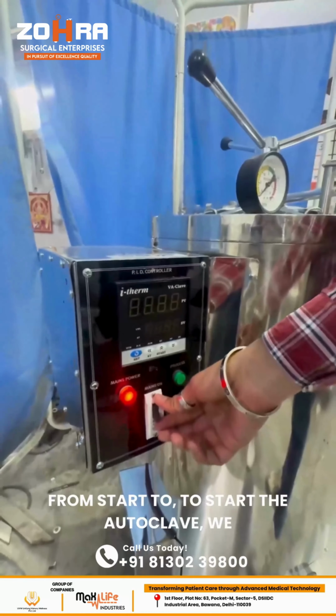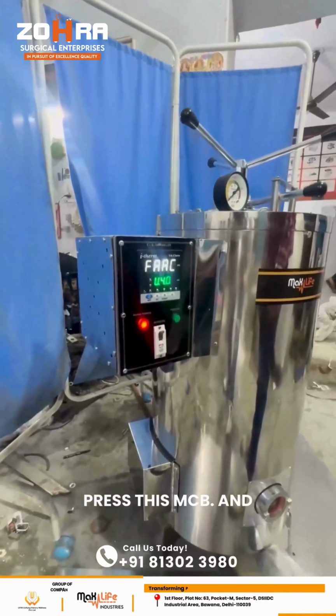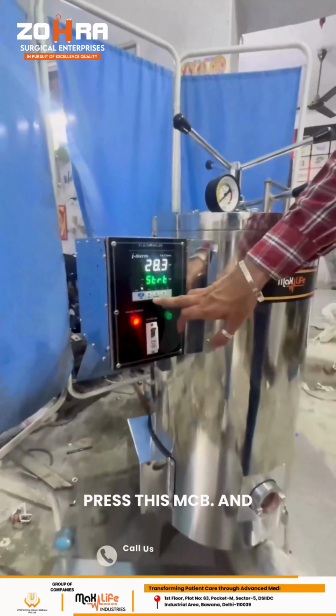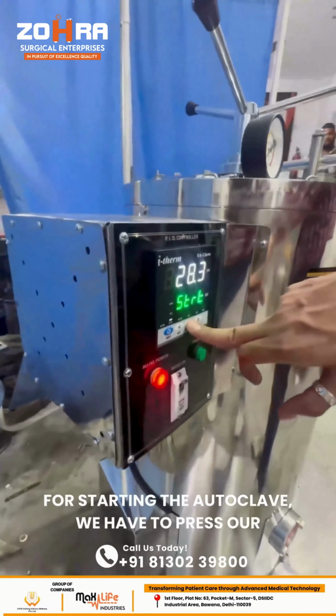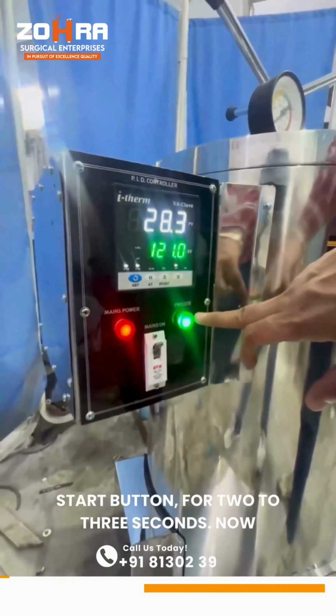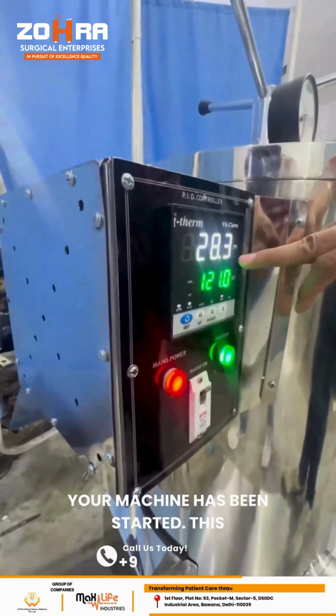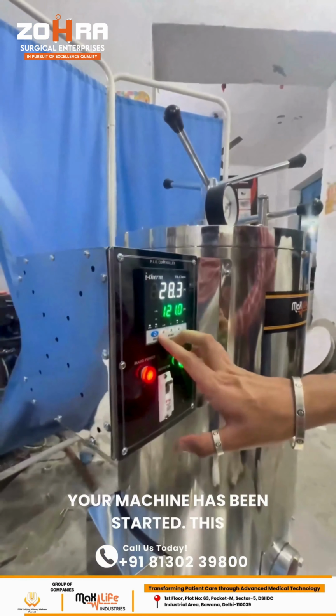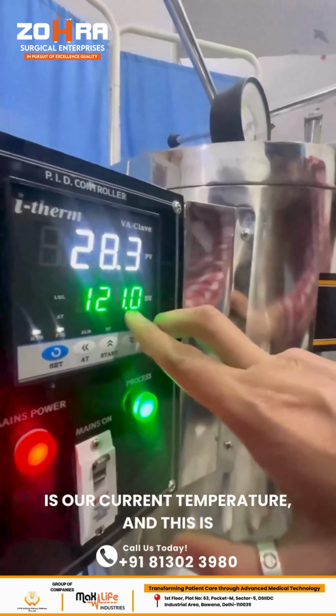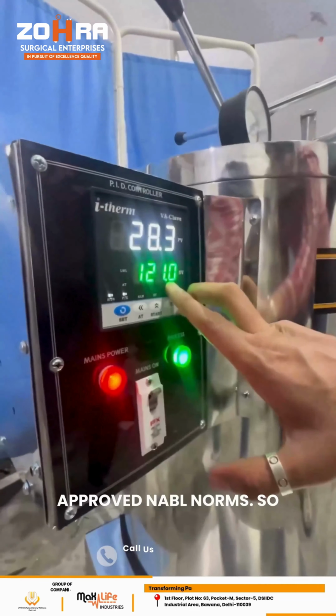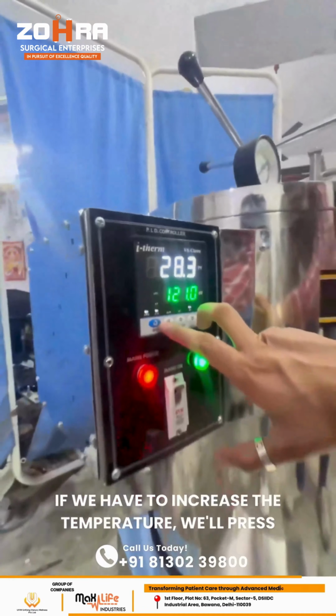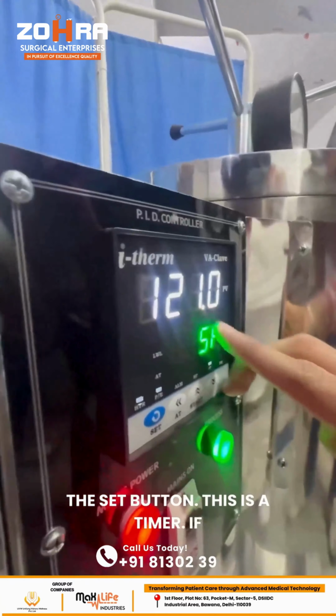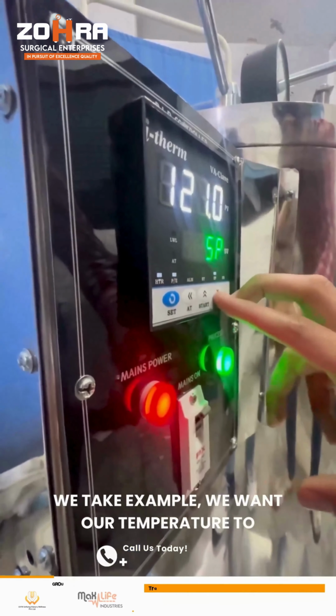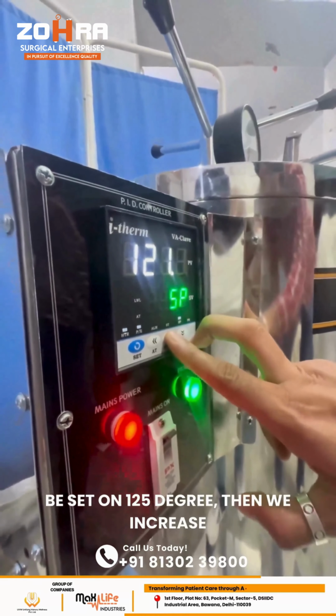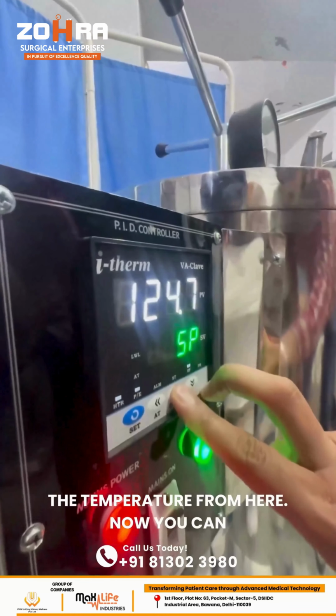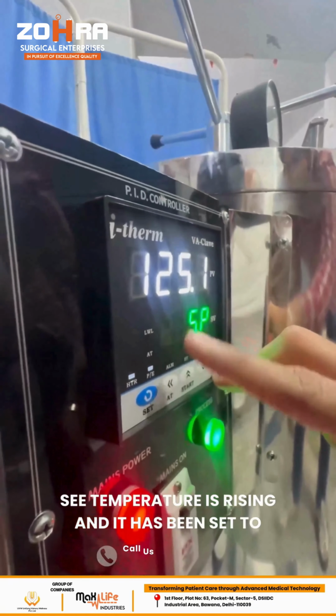To start the autoclave, we press this LCD. And for starting the autoclave, we have to press our start button for 2 to 3 seconds. Now your machine has been started. This is our current temperature, and this is we have set in 121 degrees, which is approved by the NABL norms. So if we have to increase the temperature, we'll press the set button. This is a timer. If we take example, we want our temperature to be set on 125 degrees, then we'll increase the temperature from here. Now you can see temperature is rising and it has been set to 125.1 degrees.